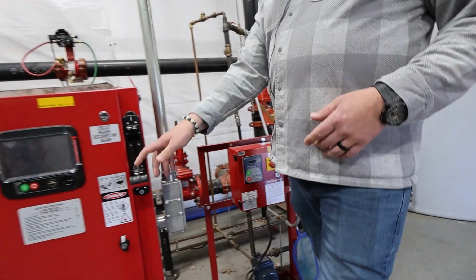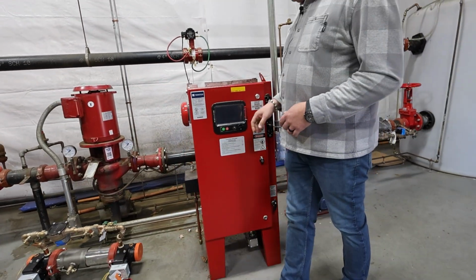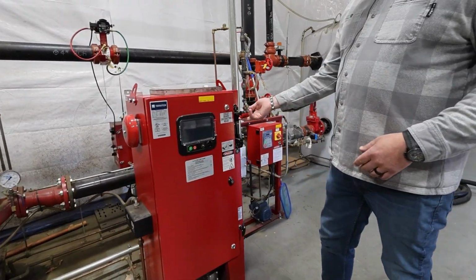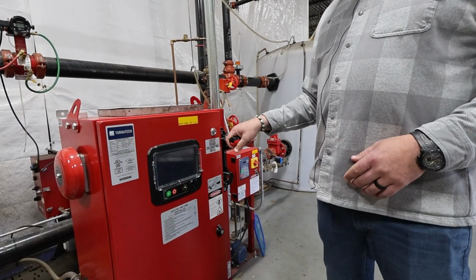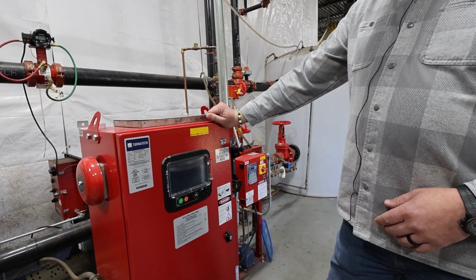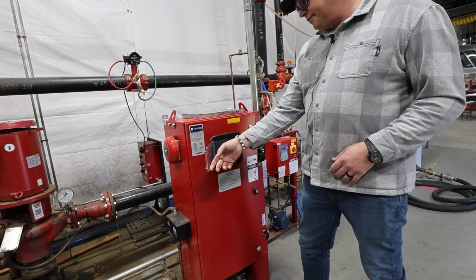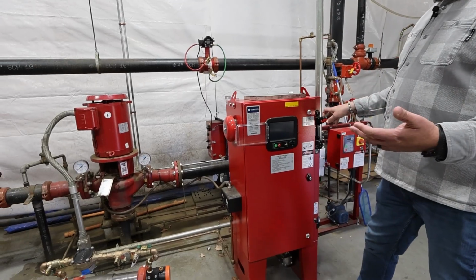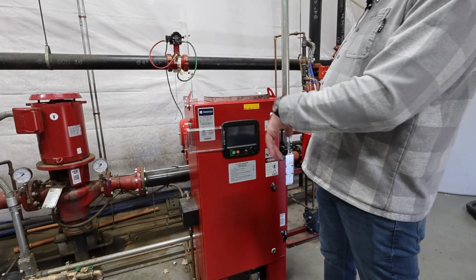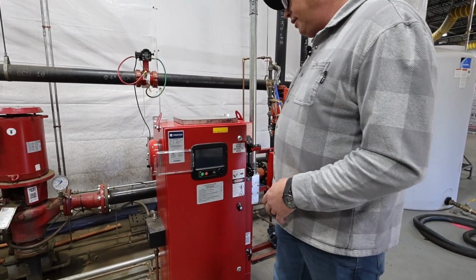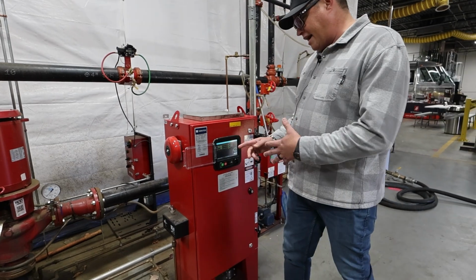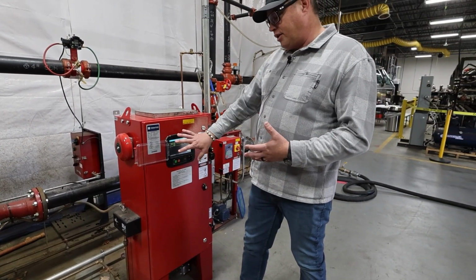We have that off right now. Now we're gonna check our main fire pump. So we're gonna pull up on our circuit breaker to turn on the fire pump controller. And if this is already low on pressure, it's gonna go ahead and start and kick on the pump. It has an automatic shutdown enabled on this controller.